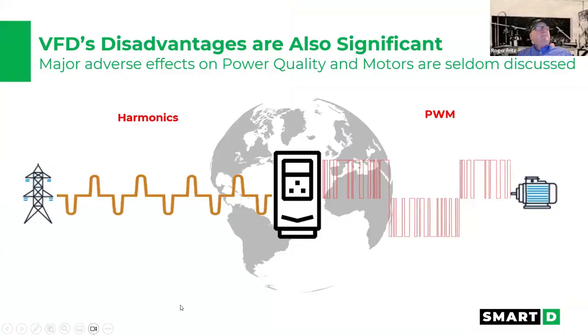So it does create these pulses in the input, and that's what they're calling harmonics. You have 60 cycle power, but when you have these pulses happening as it draws nonlinearly into the DC bus compared to load, you get ripples, and these ripples change back and forth, and that's where the harmonics show up on the input side going to the power source.